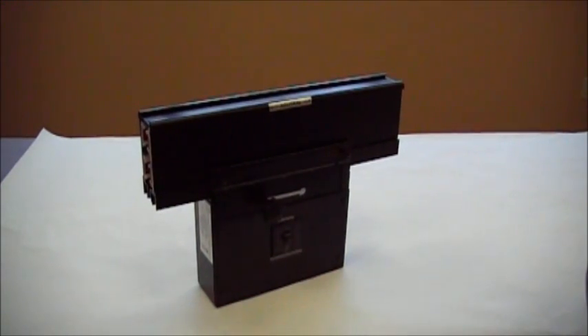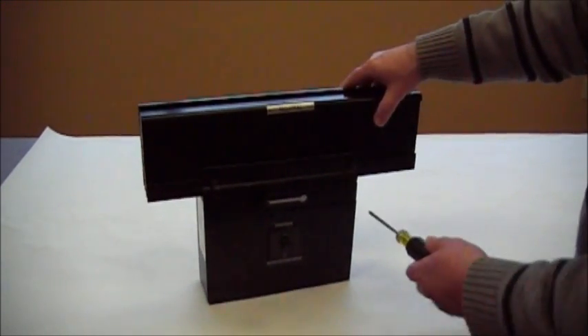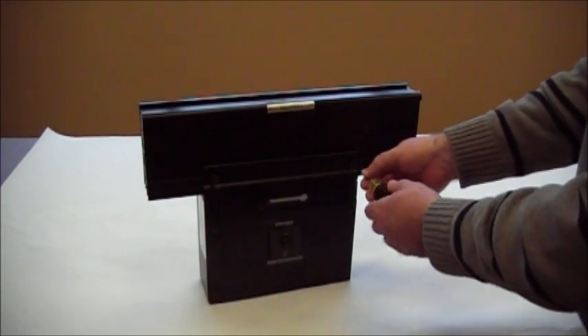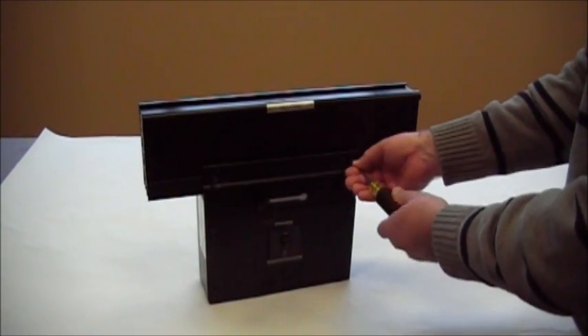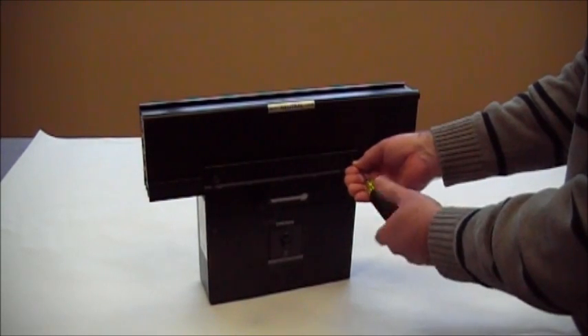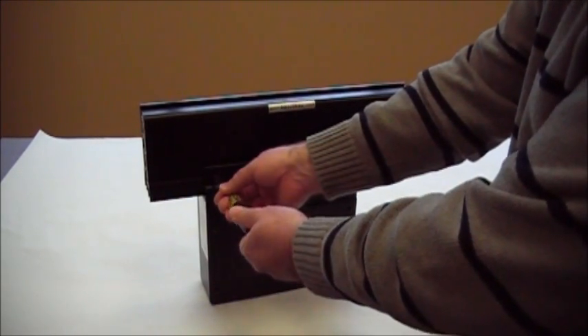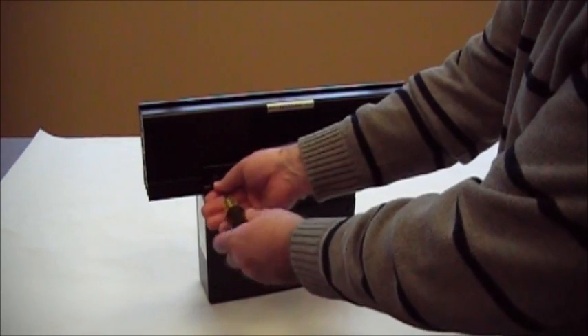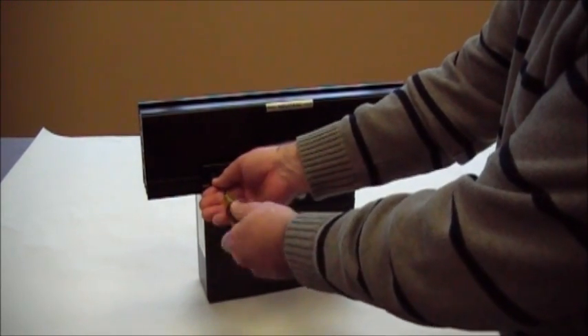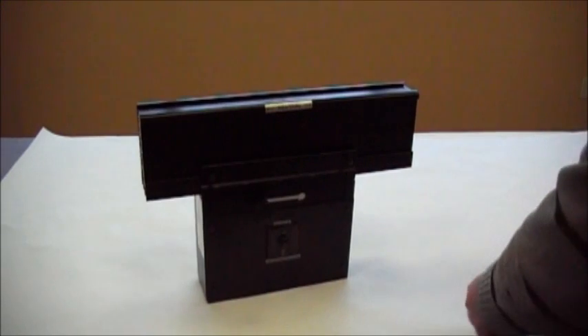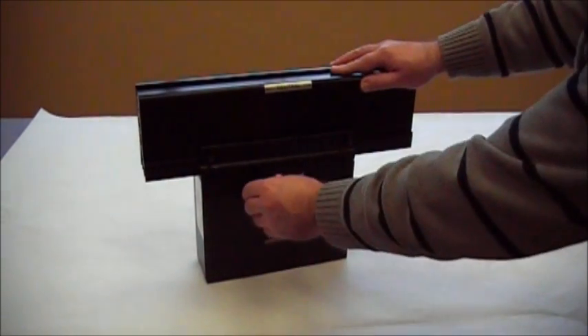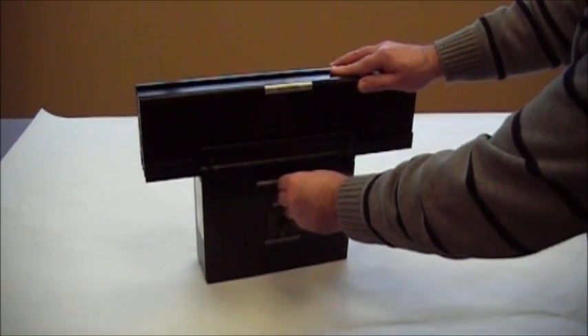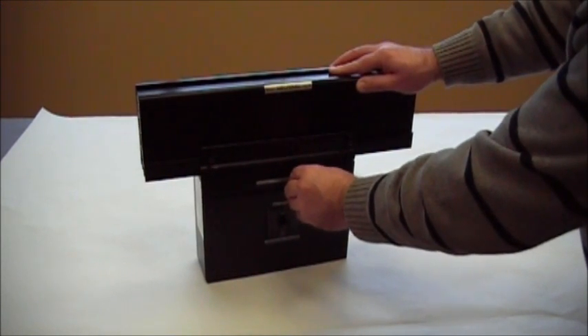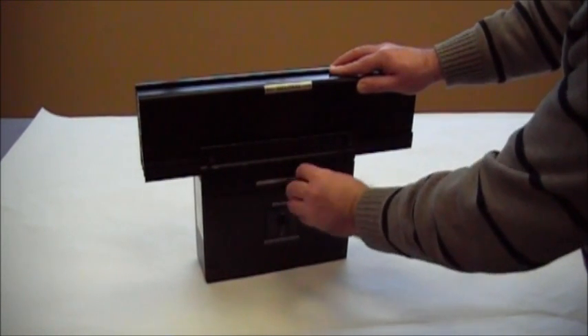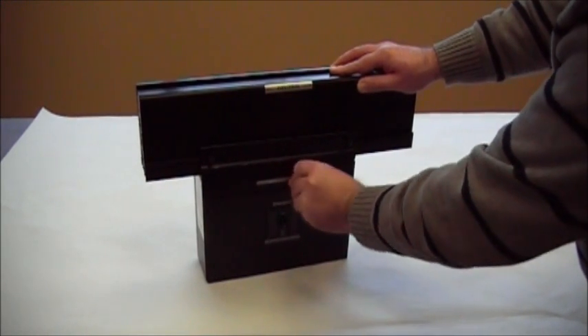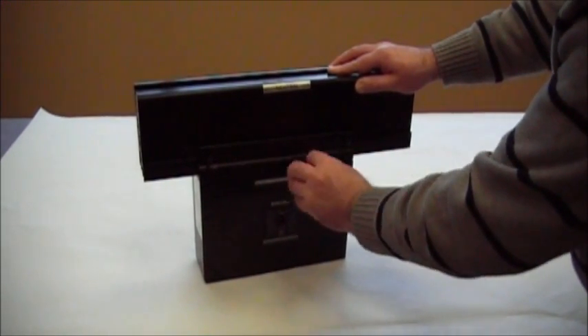Once it's fully engaged, the two screws will be secured to the side of the busway itself to secure that in place. Once that's done, the lever that turns the connection points into the busway is slid to the right. You can tighten that down, which will prevent it from coming back out or being moved accidentally.